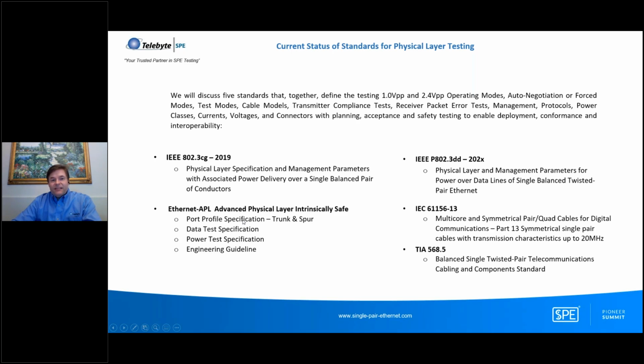Then we have the Ethernet Advanced Physical Layer, APL, for intrinsically safe testing and also non-intrinsically safe environments. They have a number of specifications that you can follow for testing. We're going to focus on 4 right here. There's the port profile specification, and this defines power classes, especially for deployment of equipment on an APL certified network. You have trunk lines that can be long lines up to 1,000 meters, or spurs that can be up to 200 meters that you're running the remote devices on. Spurs are defined to operate in a 1 volt peak-to-peak operating mode, and trunks can be higher voltage, the 2.4 volt peak-to-peak mode. They also define data tests and power tests, and then there are engineering guidelines for best practices and for installation and deployment of the equipment.